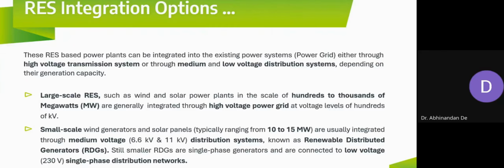Or the high voltage transmission system, which is 33 kV and beyond. It all depends on what amount of renewable energy we wish to integrate into the existing power grid. If it's a small amount of power, maybe in the range of a few hundred kilowatts, we can go for low voltage integration. Many rooftop solar plants and small scale wind generation can be integrated even at the distribution level, meaning the 415 volt three-phase system.